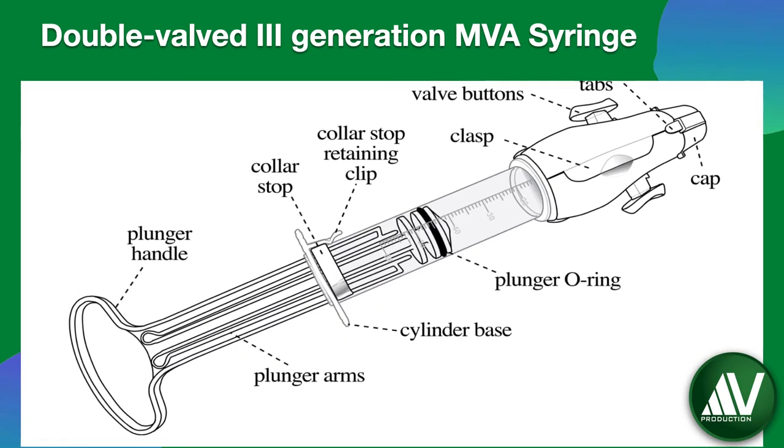Currently, for manual vacuum aspiration, a third generation IPAS MVA Plus aspirator is used as shown here. It is composed of the following parts: a valve with a pair of buttons that control the vacuum; a cap and a removable liner; a plunger with a plunger handle and O-ring; and a 60 cc cylinder for holding evacuated uterine contents with a retaining clip for the collar stop. The IPAS MVA Plus aspirator provides a suction pressure of between 24-26 inches or 610-660 mm of mercury.